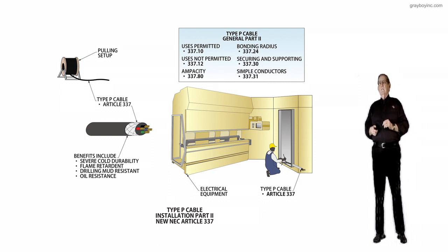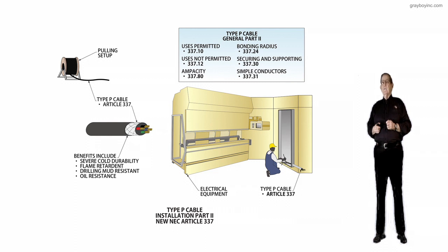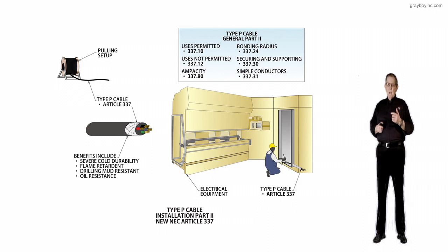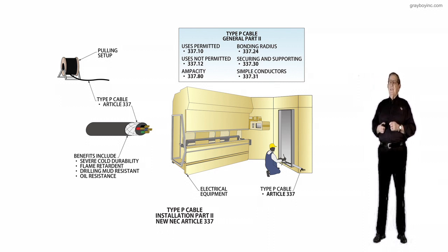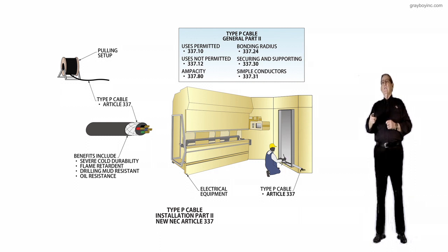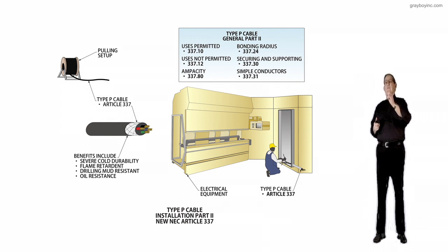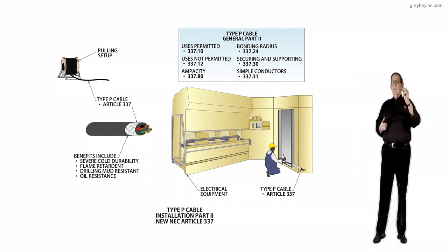Now, the simple conductors that we use, and most of the time inside these cables now, it's XHHW. You may find in some of the older cables THHN, but notice 337.31 would let you take 90-degree insulation in accordance with 337.80 in the cable, and again, repetitious, but you could derate from that 90-degree back to 60.